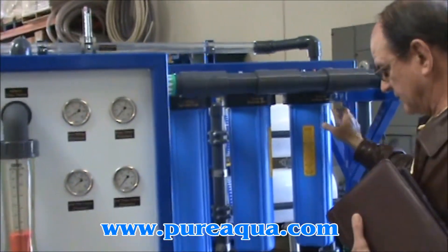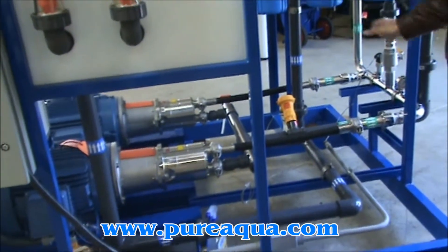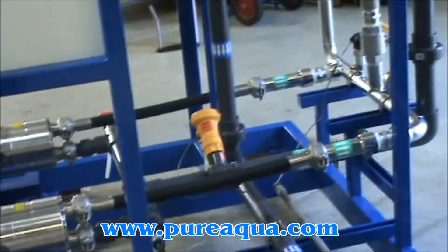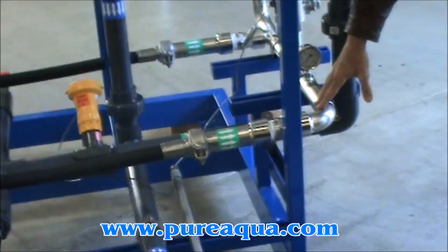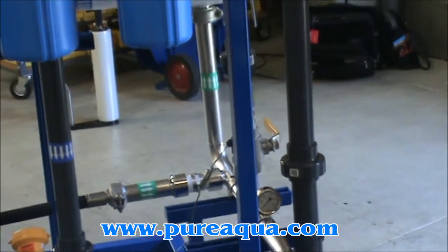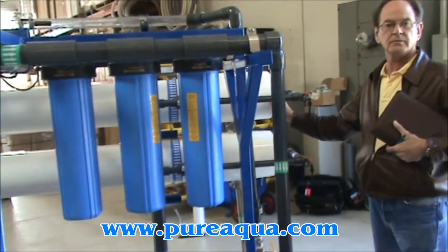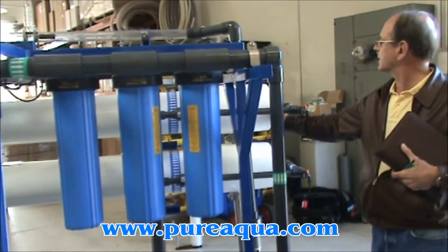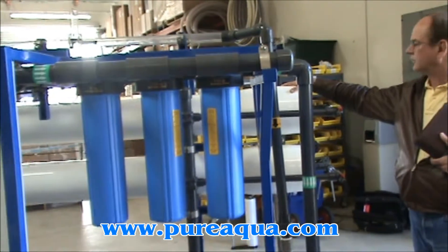From there, the feed goes to two 20 horsepower motors with stainless steel pumps. You can see that the feed water piping is electropolished stainless steel. We feed two vessels in parallel; each vessel has four 8-inch diameter Hydranautics seawater membranes. The pressure vessels are a Prototec brand, made in the United States and rated to 1,000 PSI.